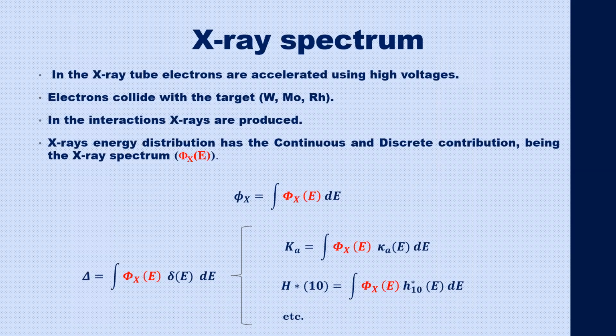But why is the X-ray spectrum important? Well, knowing the spectrum allows us to calculate the total fluence rate, and also any dosimetric quantity. The only other information that we need is the fluence to dose conversion coefficients. If these conversion coefficients are the kerma, then using this integral we can calculate the air kerma. If these conversion coefficients are those related to the ambient dose equivalent, using this integral where the spectrum is included, we come out with the ambient dose equivalent and any other dosimetric quantity that we want to calculate or determine.